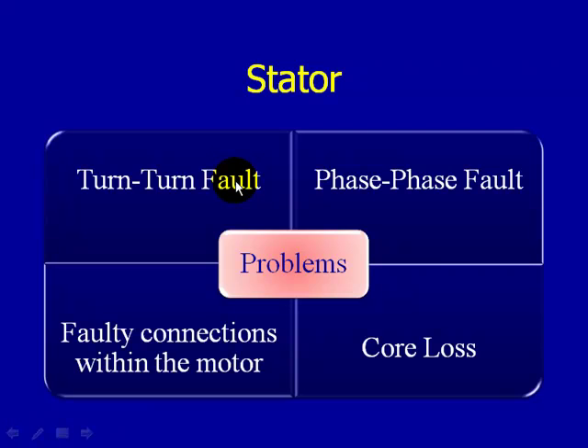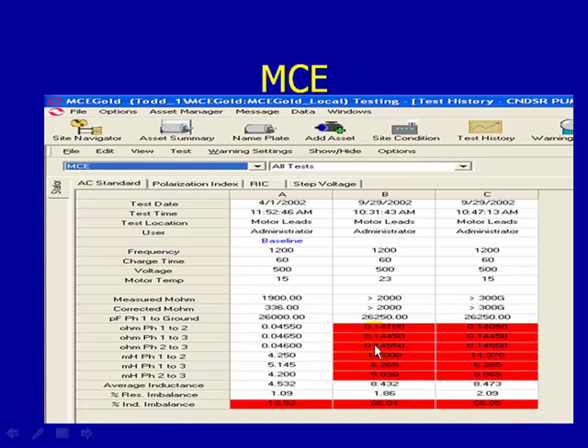Another thing that could cause a turn-to-turn or phase-to-phase fault is possibly high vibration, where it rubs away at the insulation. Also consider the rotor fault zone — if you have an anomaly in the rotor, it could be creating high heat, and since the rotor is very close to the stator, that excess heat could degrade the stator insulation. Faulty connections within the motor include dead or faulty solder connections. Core loss, or loss of core lamination, also generates excess heat that could destroy insulation over time and cause a potential fault inside the stator.